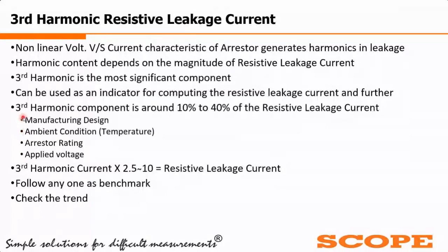What generally remains unknown is the manufacturer's design, and what factor is to be attributed to this design parameter in this correlation. So if we don't know this parameter, then my measurement will not be complete, and hence we have told you to follow anyone as a benchmark. If you do not know this manufacturing design, forget about it. Follow the third harmonic current itself from day one as a benchmark and follow the trend. Follow the trend. This is the major thing. You have to do the trending.